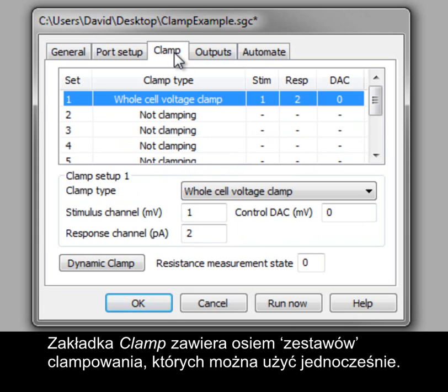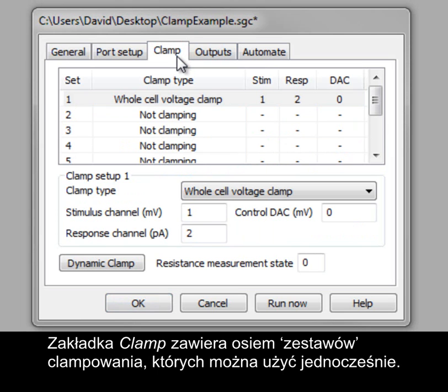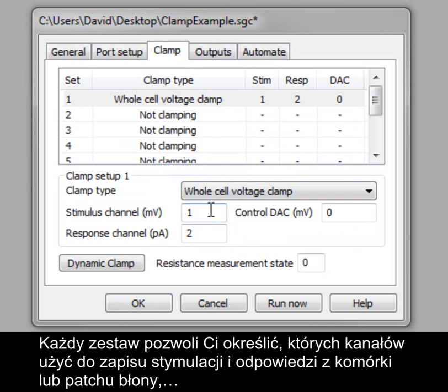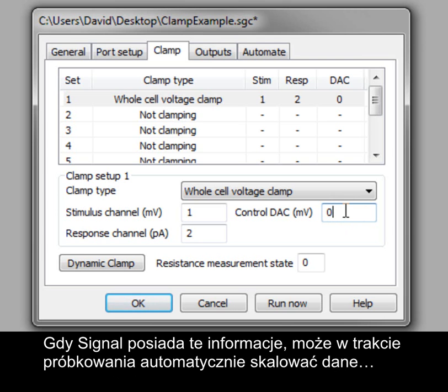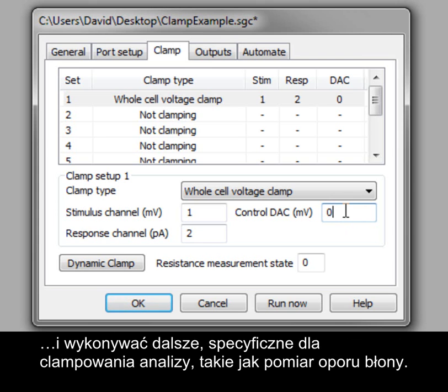The Clamp tab includes 8 clamp sets which can be used simultaneously. Each set allows you to specify which channels to use for recording the stimulus and response from the cell or patch, and which DAC output should be used to control the stimulus for the selected experiment type.